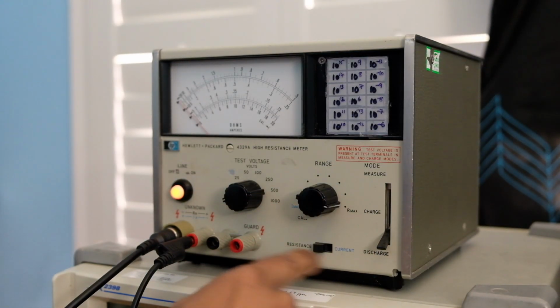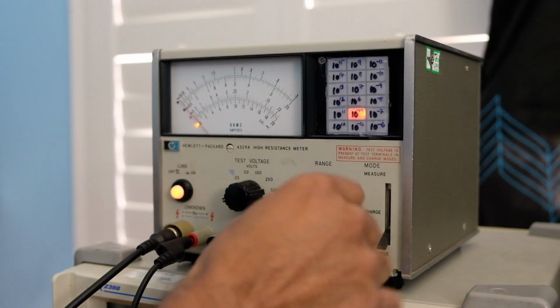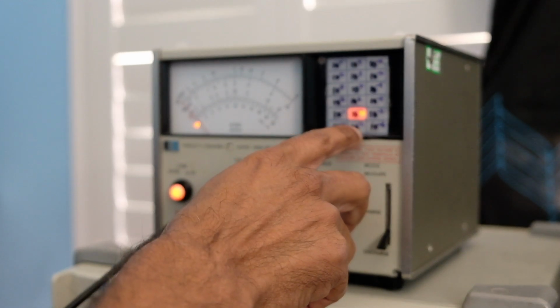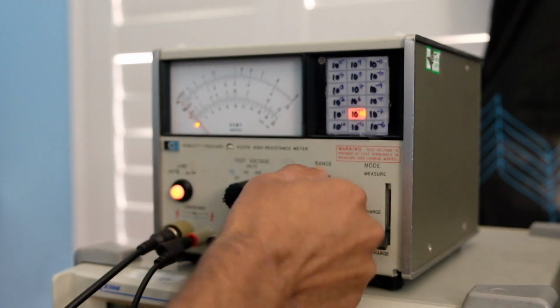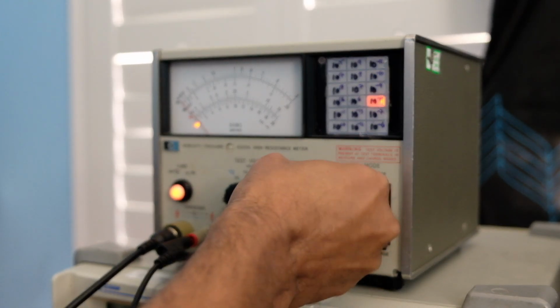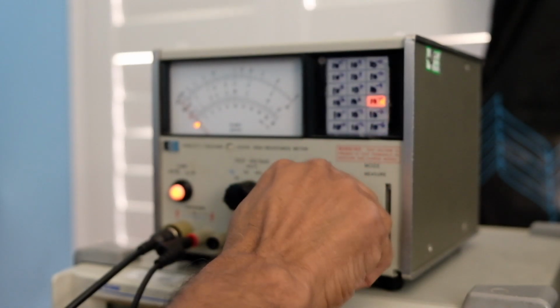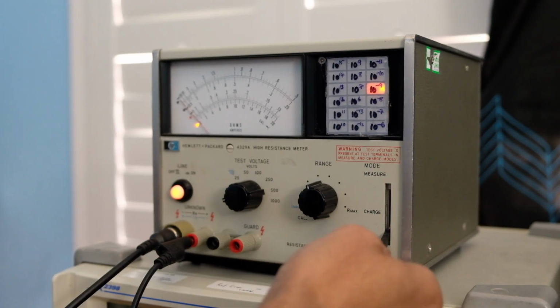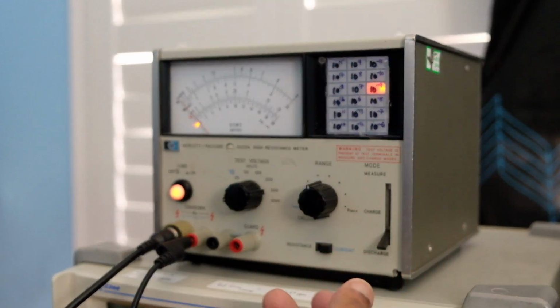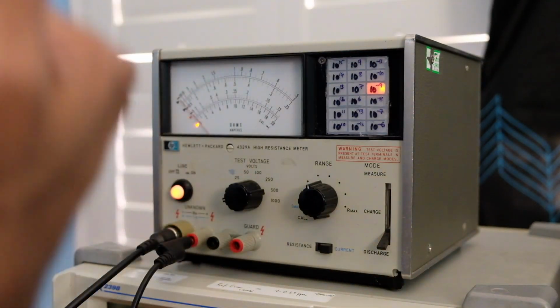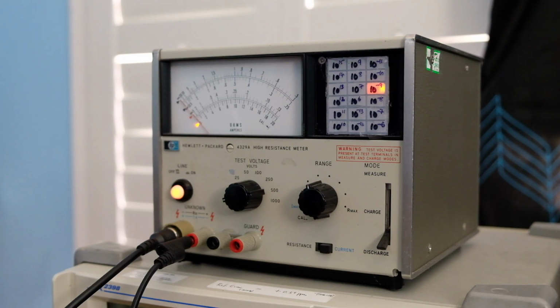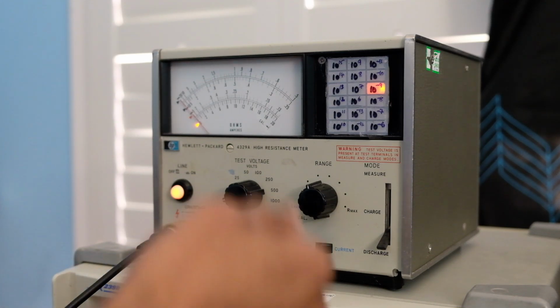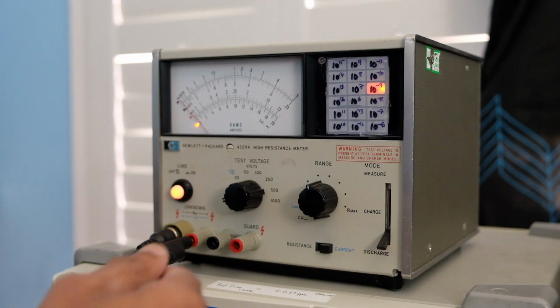Similarly, if you switch the current, you'll be able to see the current scales. The minimum current is 1/10 of a picoamp, and you can go to the highest current, which is a microamp reading. The way it works is you first charge the device and then you do a measure. It sets the DC level, and if you're measuring a capacitor, for example, you may want to first charge it to get rid of all the initial charging current, and then you can do a leakage test on the capacitor.